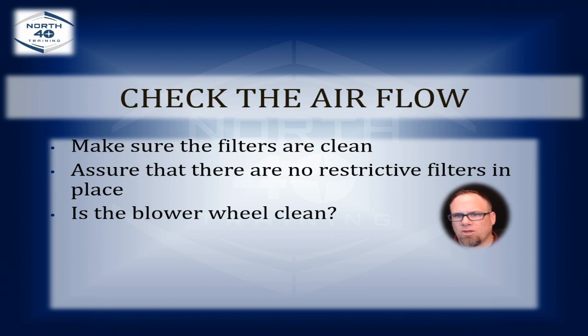Is the blower wheel clean? Now, ASHRAE and ENERGY STAR both place a number on the percentage of decrease in airflow on the return side or the supply side as to whether or not it's going to affect the rest of the system. And that's 10%. A 10% restriction on either the supply side or the return side, both can be affected by the blower wheel, can affect the overall efficiency and capacity by up to 50%. That is so huge and such an easy thing to fix and to cure as well.